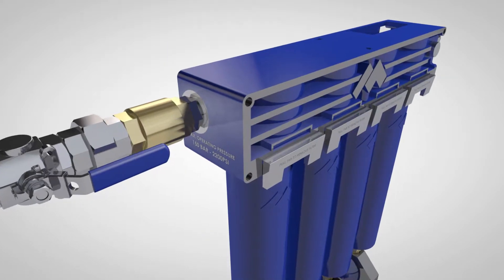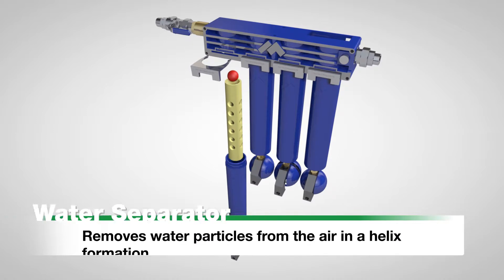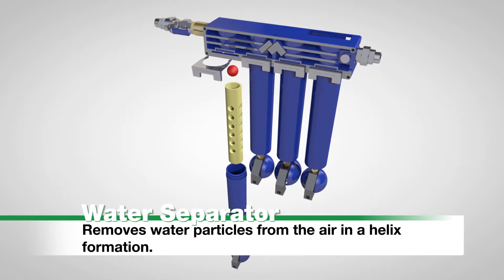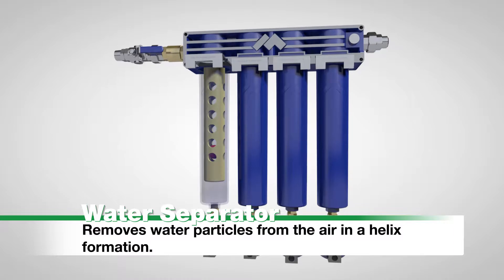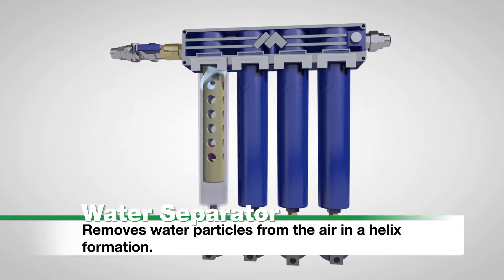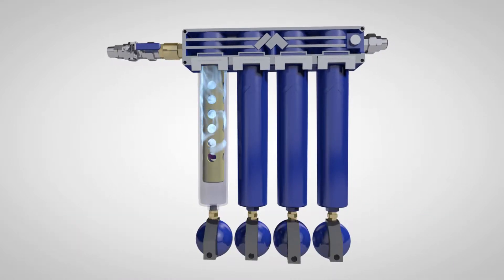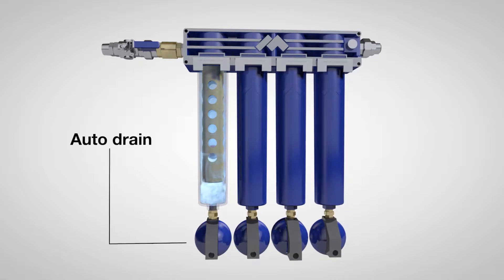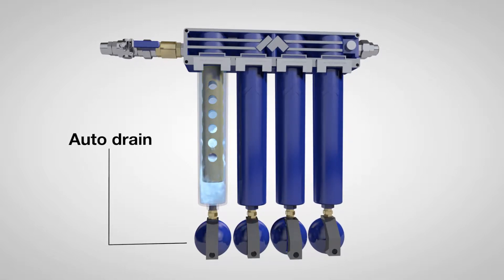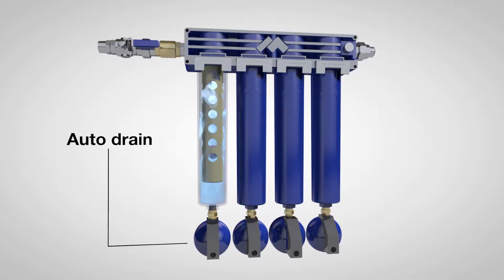The first stage of filtration is water separation. The filter directs the flow of compressed air in a helix formation, separating water particles from the air. Excess water is collected in the auto-drain where it is automatically pressurized and purged based on water head levels.